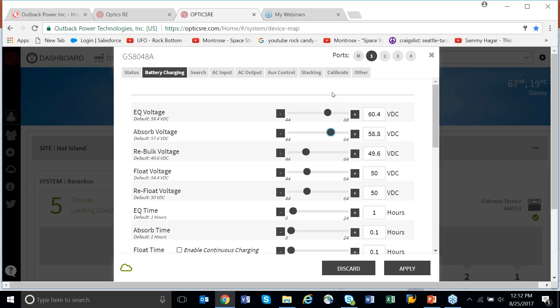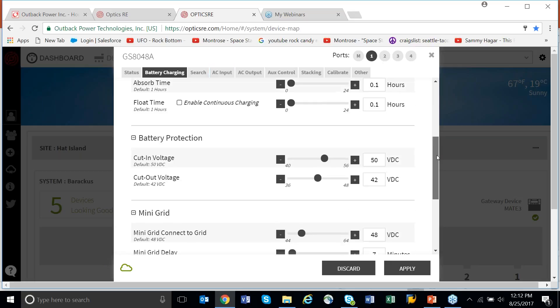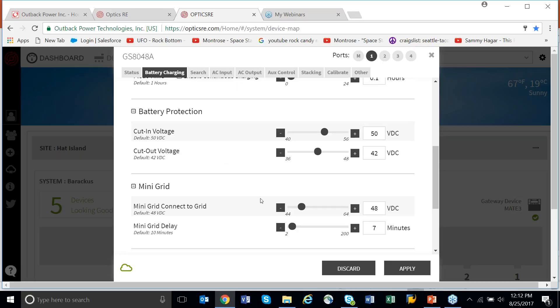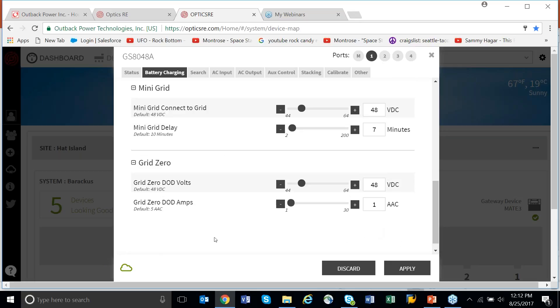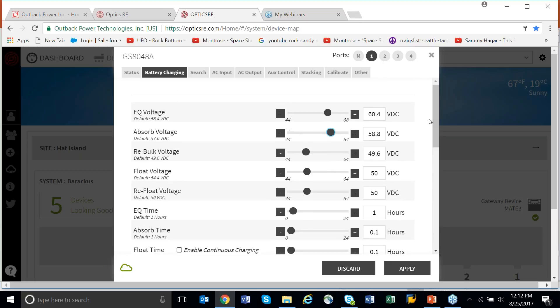This is really huge — how often do you forget something? You come back, wake up in the middle of the night, your eyes are burning holes in the roof going 'oh I forgot to do that.' You can come back in, look at it, and make the changes. Down below you can see the battery protection cut-in and cut-out voltages. You can make adjustments to the mini-grid mode and to the grid-zero mode. All these things can not only be called up and adjusted, but installed and integrated into the system.